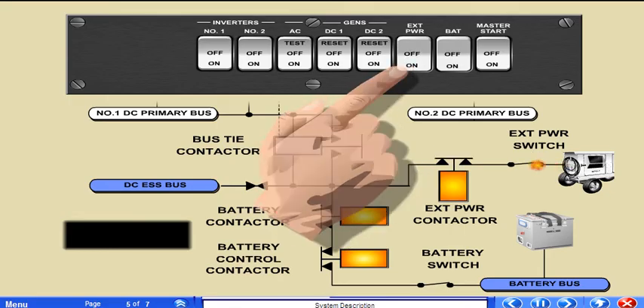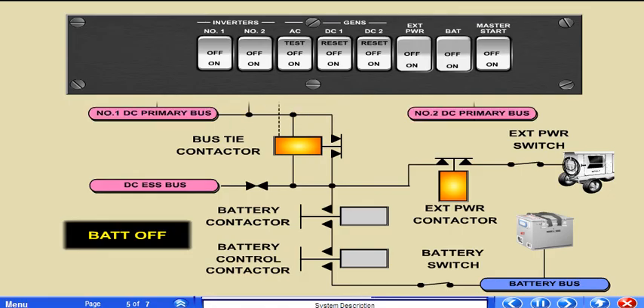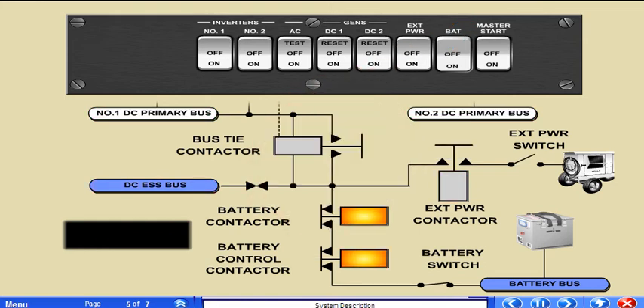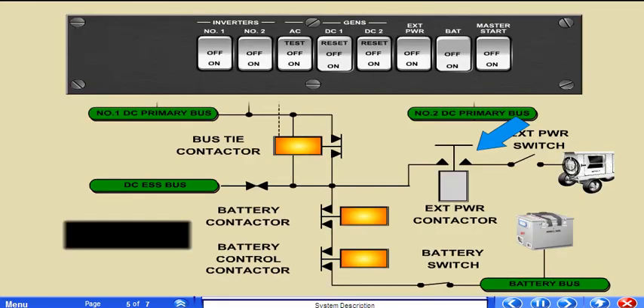The 2-position external power switch controls the external power connection to the helicopter. The on position connects the external power to the entire DC system except the battery bus. The battery cannot be charged with external power. The off position disconnects the external power from the DC system. The external power contactor prevents external power from energizing the DC system if one or more generators are online.